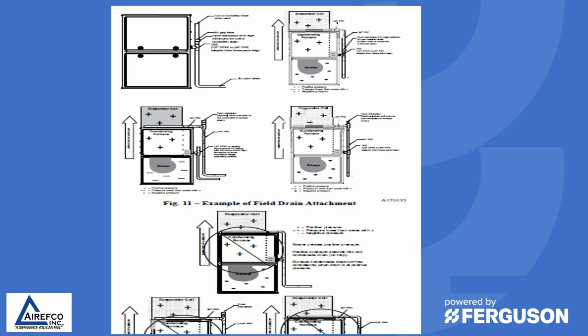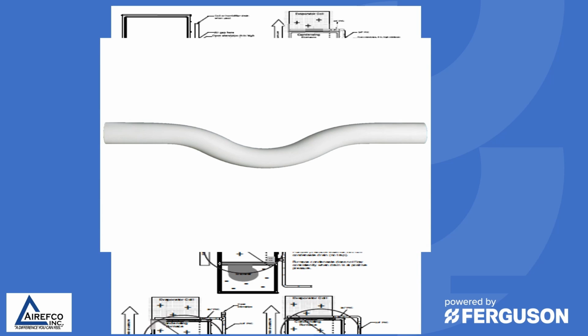Not following the manufacturer's recommendations will cause the condensate to collect in the air conditioning coil pan or to collect in the collector box of the furnace, shutting down the furnace, and also could cause water damage to the home. Never use a shallow running trap like this. This will not properly trap the coil or the furnace, and you will get water damage and problems down the road.